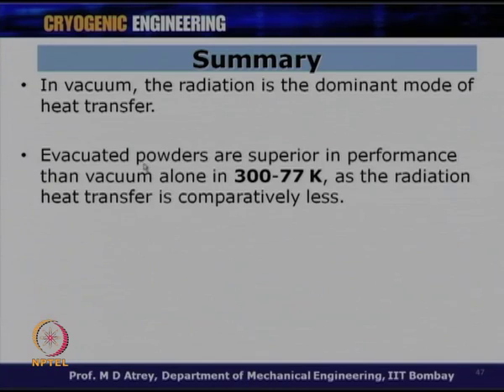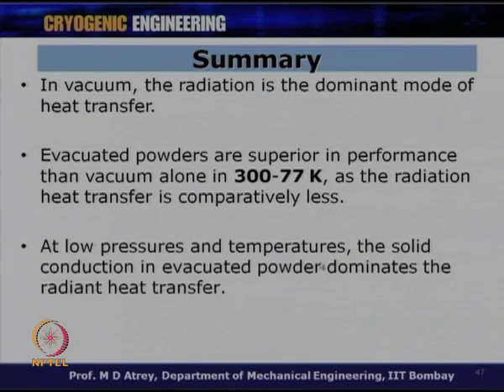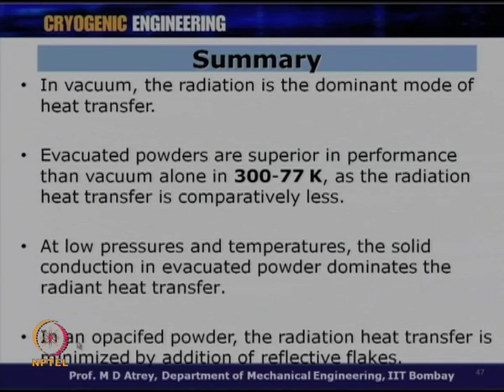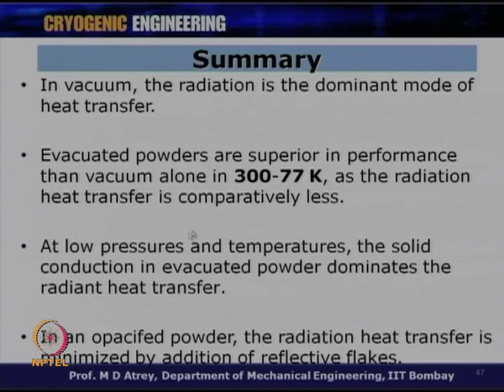To summarize: in vacuum, radiation is the dominant mode of heat transfer. Evacuated powders are superior to vacuum alone in the 300 to 77 K range as radiation is comparatively less. At low pressures and temperatures (down to helium), solid conduction in evacuated powder dominates, making vacuum alone more advantageous in the 77 to 4 K range. In opacified powder, radiation is minimized by reflective flakes, but vibration-induced packing of flakes can be problematic. Evacuated powder remains the most practical solution up to liquid nitrogen temperature.